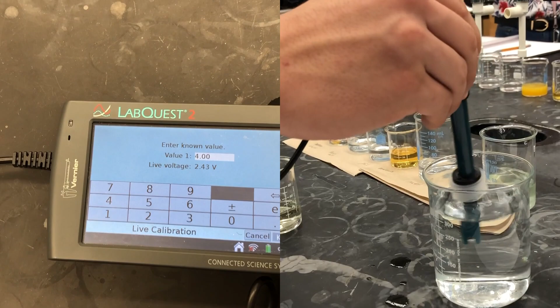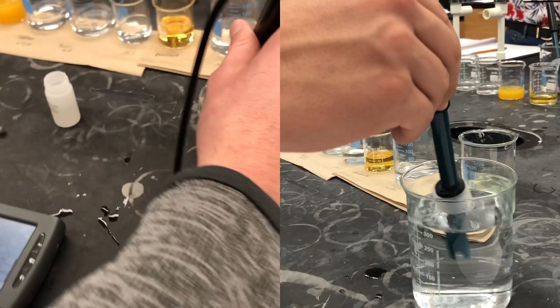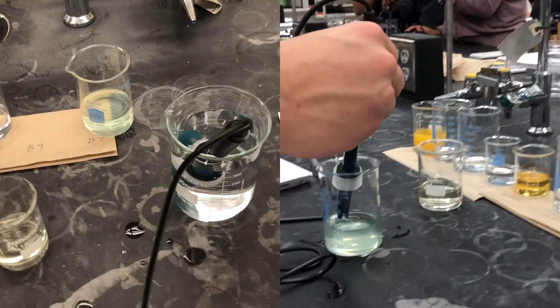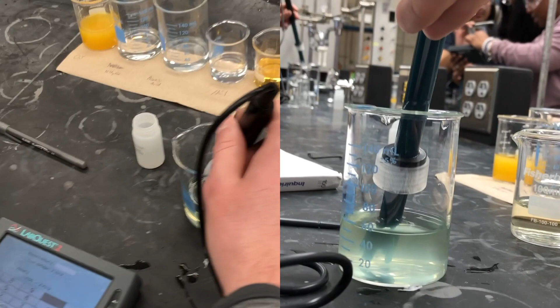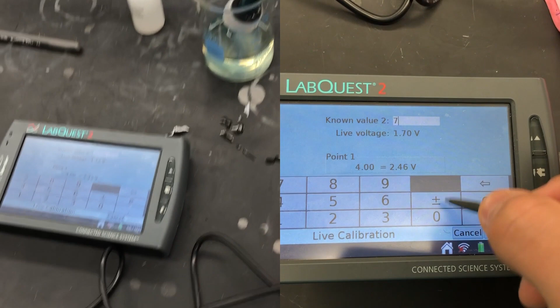Then calibrate now. Then enter value 1 as 4.00. Wait until the voltage is stable, then press Keep. Next, rinse the probe. Then submerge the probe in buffer pH 7. Enter value 2 as 7. Wait until voltage is stable, then press Keep.